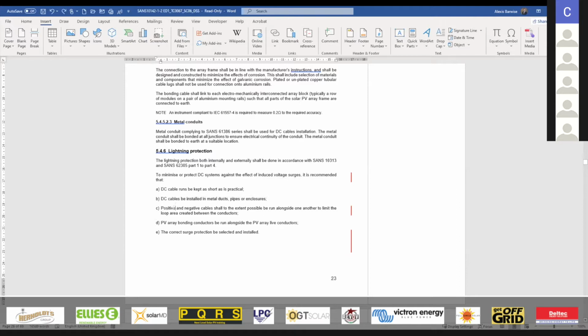The second or the third item is to keep the cables right alongside one another in order to limit the loop that is created. Now, again, this is quite an interesting one. We've had many sessions with the big EPCs saying that from a solar side, it's easier to just run a positive all the way through and then bring one negative back, and you end up making long loops. But we are advising again that the shorter we can keep the loop, the better. The loop is the area between the positive and the negative, so area is the length times the width. The width would be the spacing in between, and the length would be the length that these parallel conductors are running. The larger the loop, the larger the effect of a transient or an induced lightning strike, so it's almost like exciting, creating higher overvoltages. Hence it's good practice to keep these cables alongside one another.